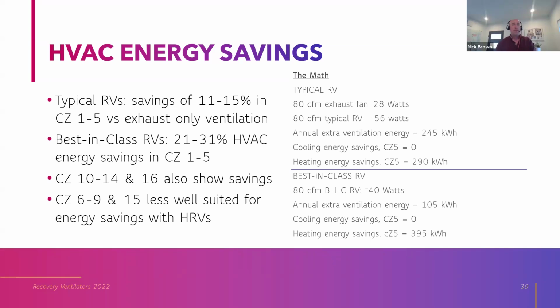We did a study where we looked on an hourly basis across all 16 climate zones in California, the outdoor temperatures, the indoor temperatures, how much of that delta T gets recovered by the recovery ventilator. And we looked at typical recovery ventilators, which generally have higher watts per CFM and lower recovery effectiveness. And we looked at best-in-class recovery ventilators that have better numbers on both of those. We found savings of 11 to 15% in climate zones 1 through 5 compared to exhaust-only ventilation. Climate zones 1 through 5 are coastal Northern California from Eureka all the way down to, I think it goes to Santa Barbara, but not to Malibu, okay?